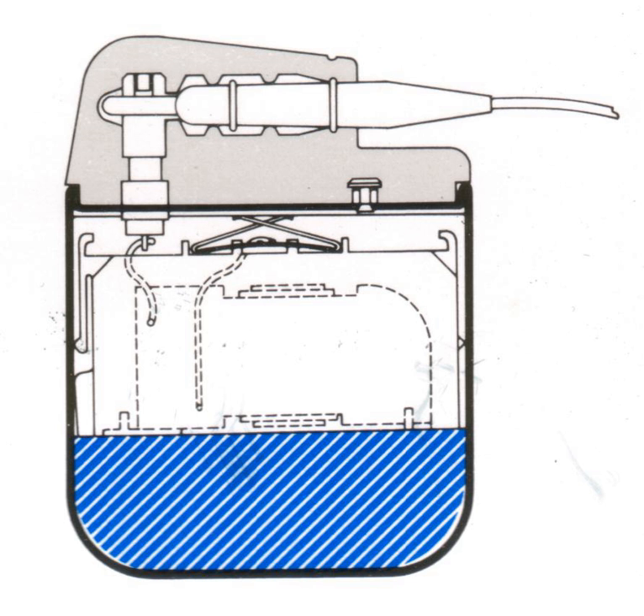These characteristics were incorporated in the next design to be implanted in humans, the Model P4, which employed 30 square millimeter area intramyocardial electrodes and later transvenous pacing electrodes, a very conservative 7.5 volt pulse, and for further conservatism, a magnetically operated switch which could be actuated from outside the body to change the pulse width.